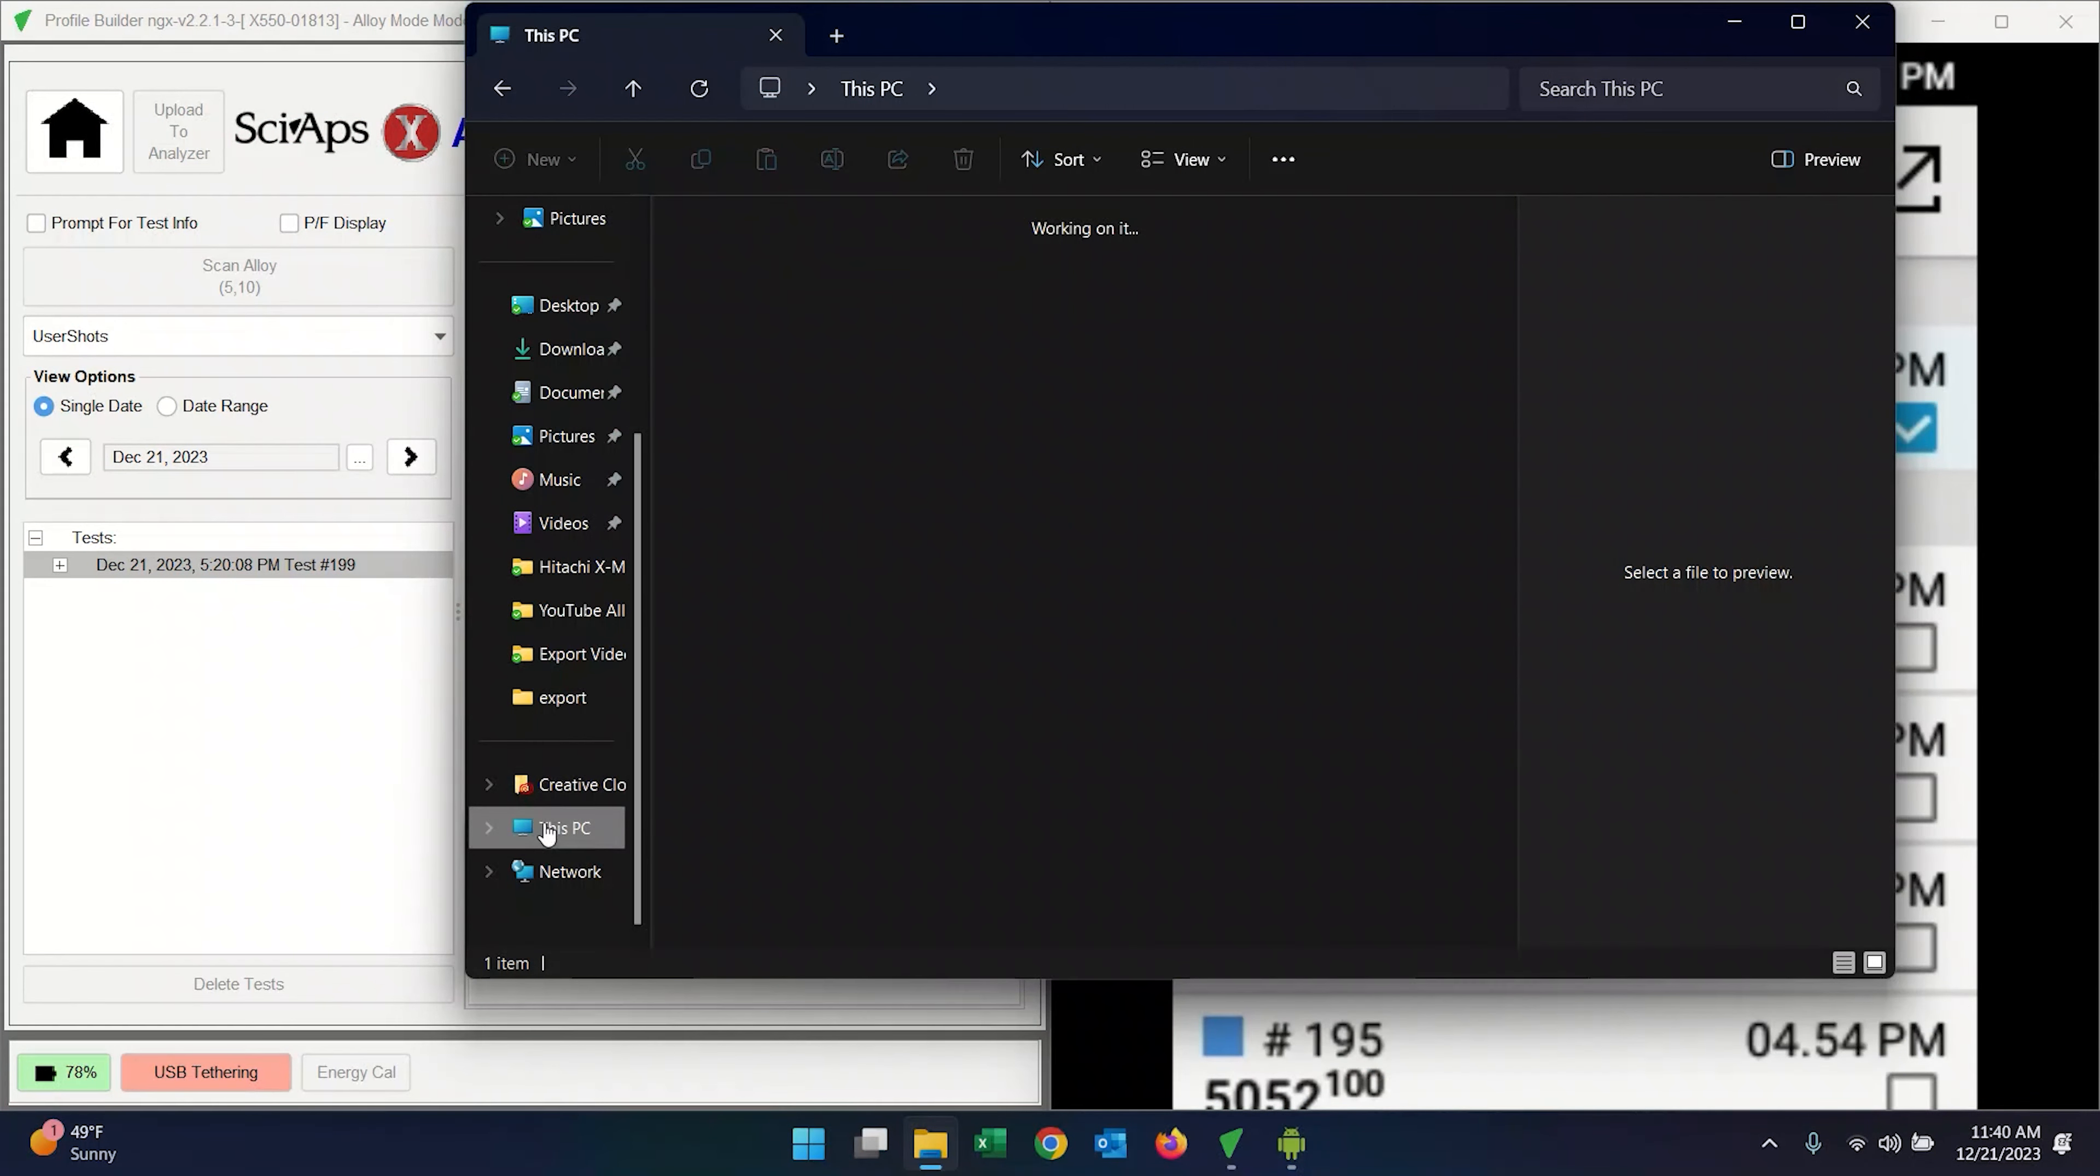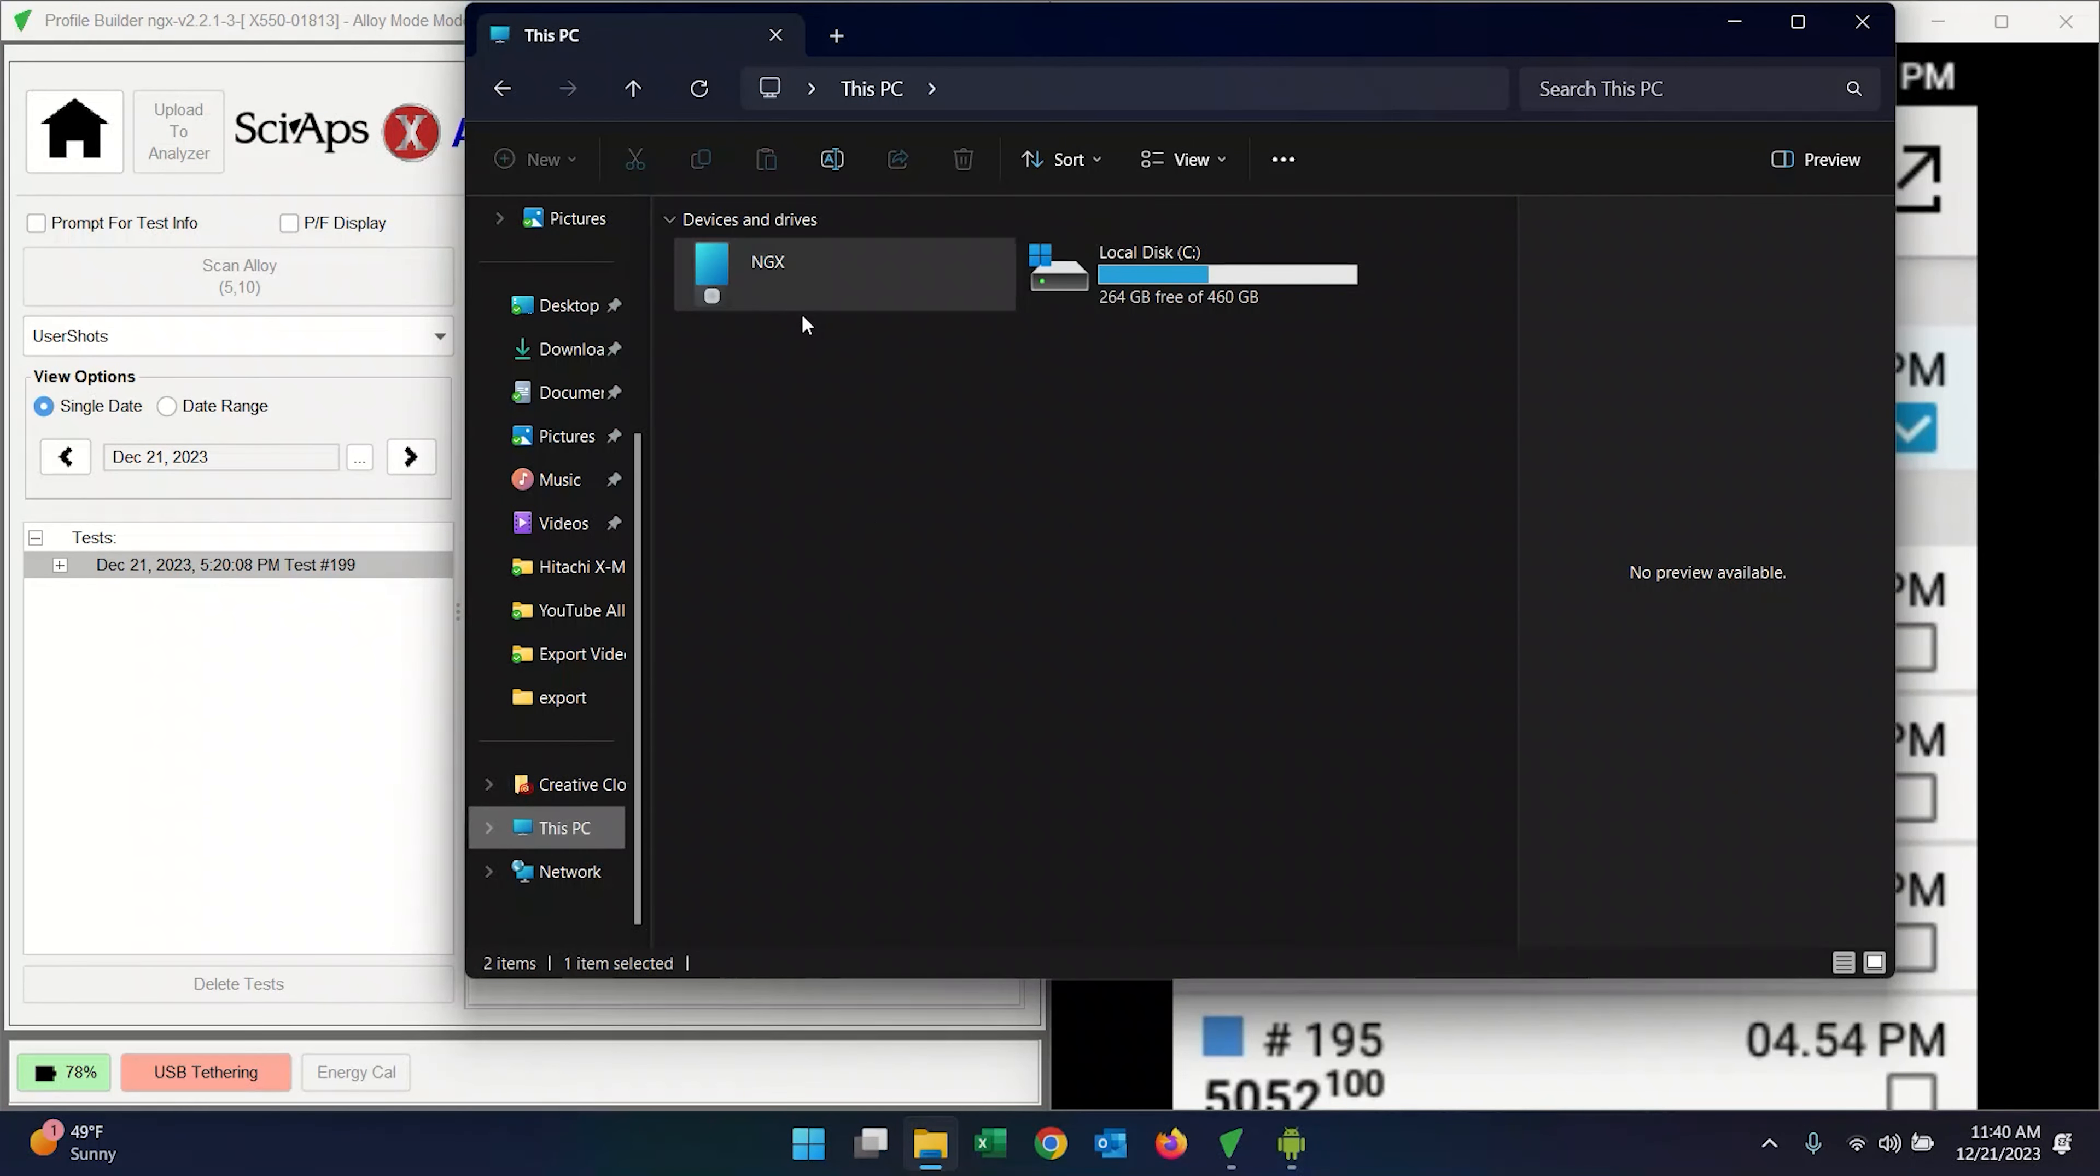Now we have the data exported to the SD card, but we need to take the data on the computer. So what I'm going to show you here is you're going to navigate to, once the analyzer is plugged in, this is the point where some people get stuck. So if you're working for a large company that has an IT department that blocks USB devices or drives, this is the point where you could have an issue with that. Talk to your IT department if you're not able to connect. It's typically just IT's blocked USB drives for safety reasons for your organization's IT safety. So just talk to them about it, make an exception for the SciAps and you can be able to move forward.